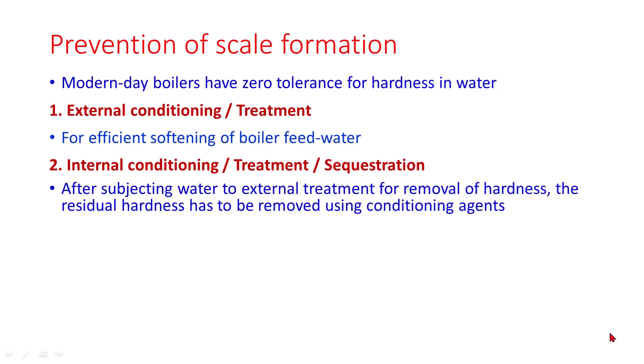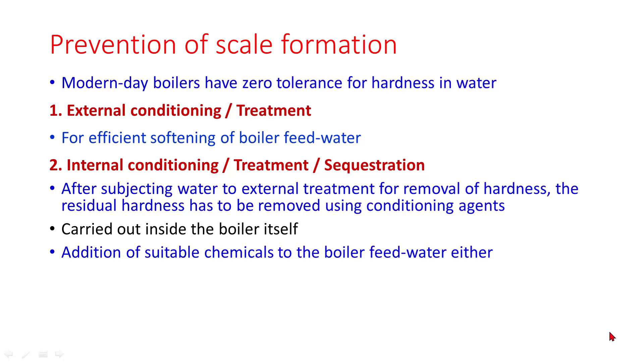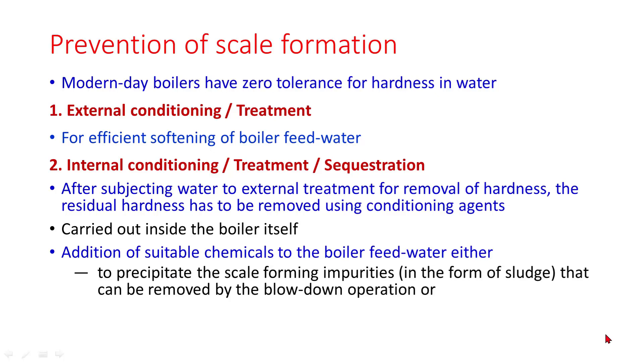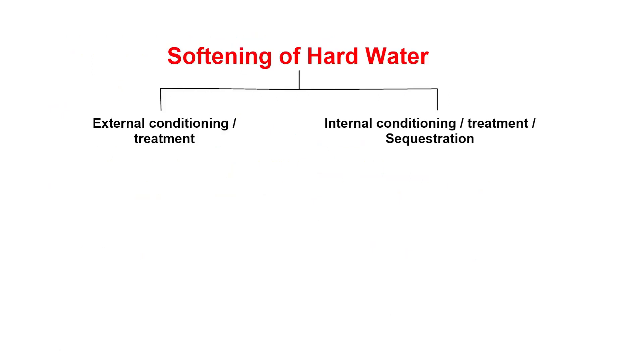External conditioning involves efficient softening of boiler feed water before the water is fed to the boiler. Internal conditioning: after subjecting water to external conditioning for removal of hardness, the residual hardness has to be removed using conditioning agents. It is carried out inside the boiler itself, by the addition of suitable chemicals to the boiler feed water either to precipitate the scale-forming impurities in the form of sludge that can be removed by blowdown operation, or to convert them into dissolved form that remains inside the water.